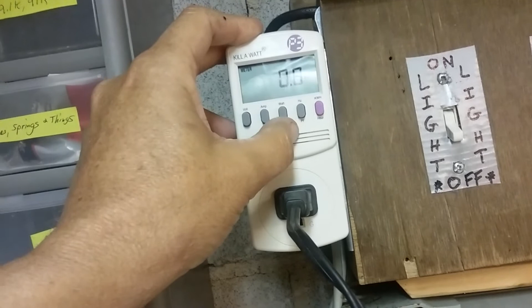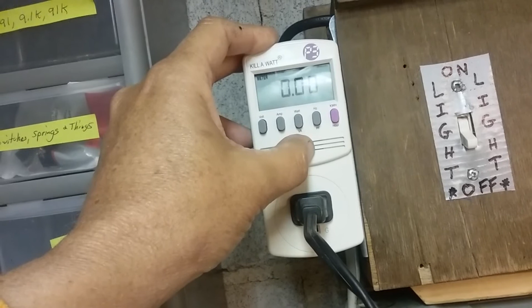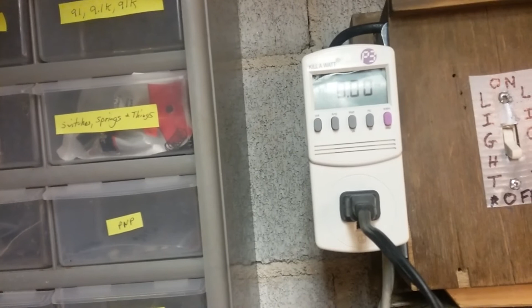There is current going through it, but this meter doesn't measure that low. So we got no wattage to speak of, not even 1/10 of a watt. We've got 1 milliamp, so it's not going to show on that meter because it starts with 10 milliamps. And that's what this would require.